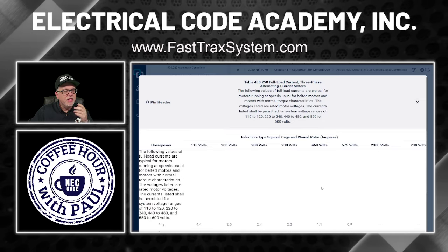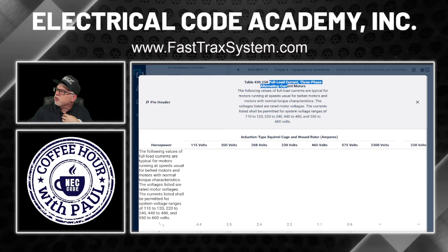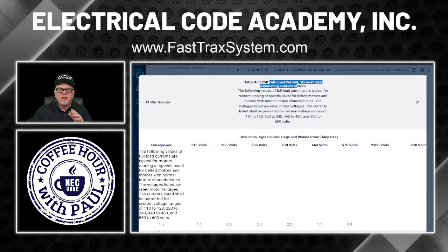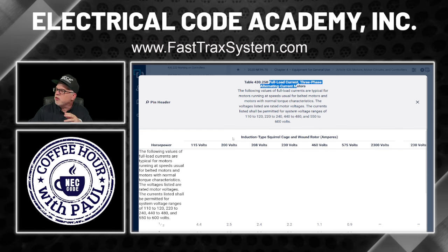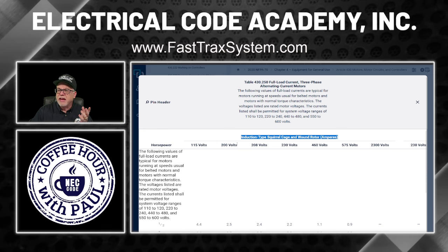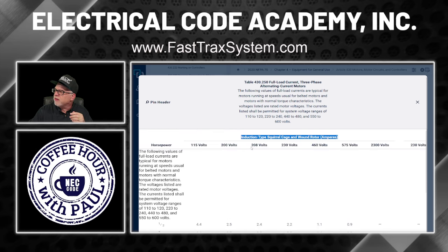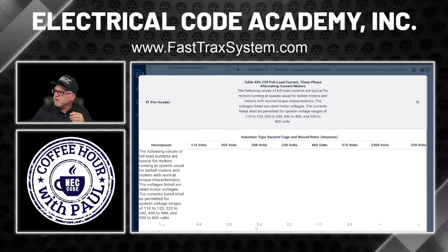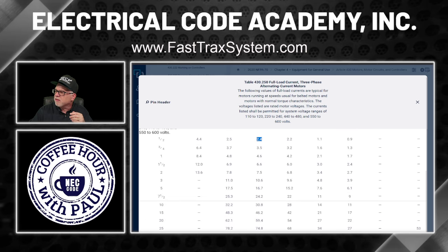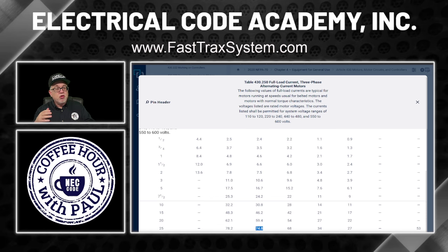Here's 250. This is most certainly what we want. Okay, this is the full load current for three-phase motors. Now, in this case, it didn't say any specific motor, so you're going to use these tables because these are the most common. And so this was a 208 volt, 25 horsepower motor. So we'll go down here. 208 is this column right here, and we come down to 25 horsepower right here. 74.8. So it's real simple, folks.